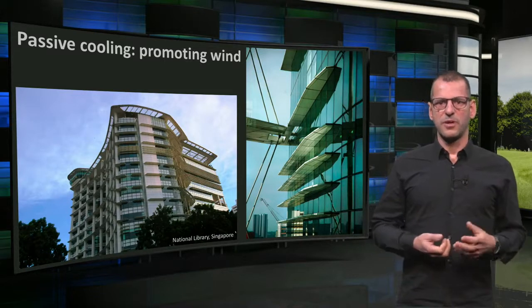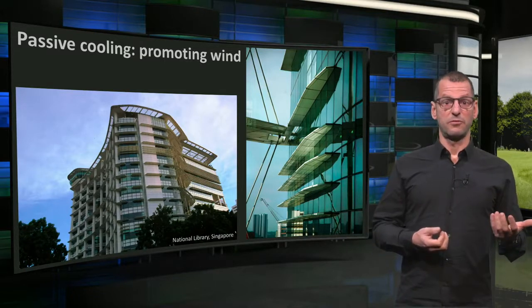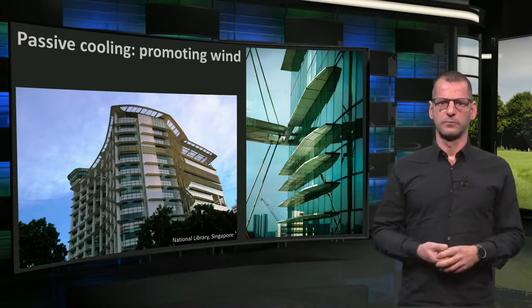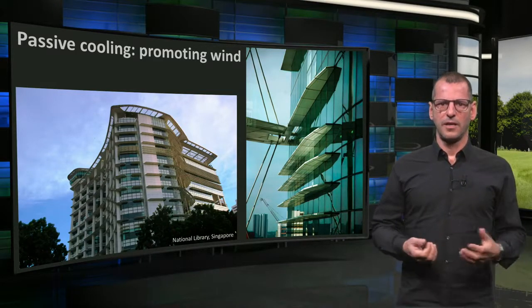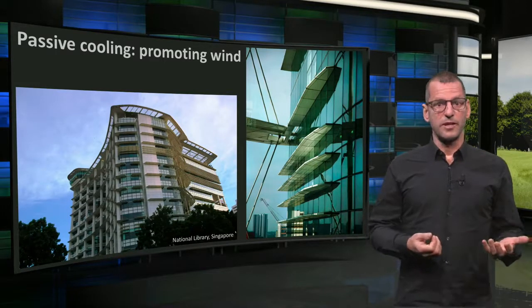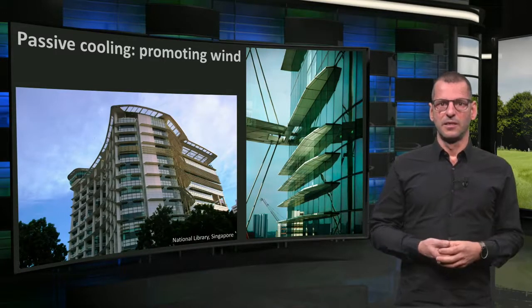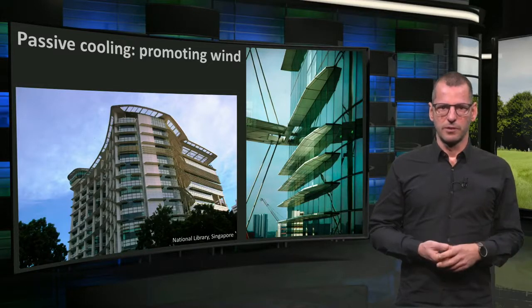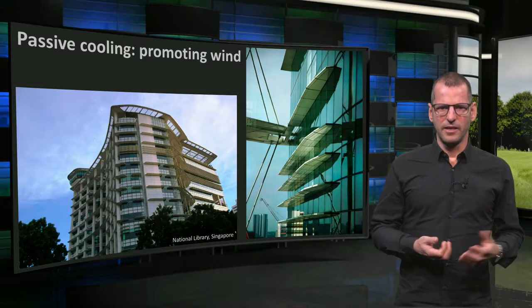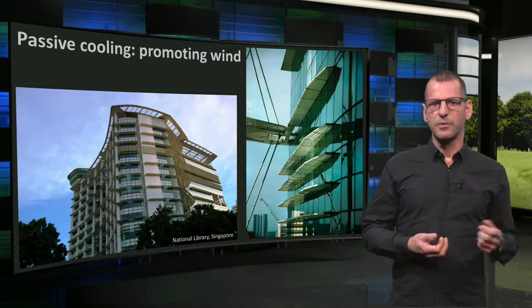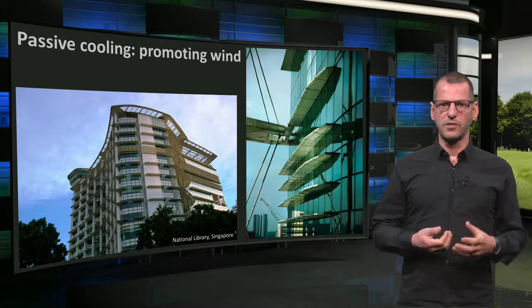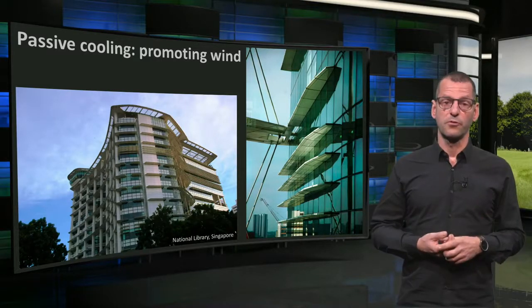Therefore, different passive solutions are needed to cool, or better phrased, to make people feel cooler. Airflows do that. The higher the airspeed, the cooler one will feel. We know this from the effect of strong winds and of fans — the sensible temperature is much lower. What the architect Ken Yeang did here was accelerate the airflow through the building by using the Bernoulli effect: a narrowing tunnel will increase the speed of the fluid or gas passing through.